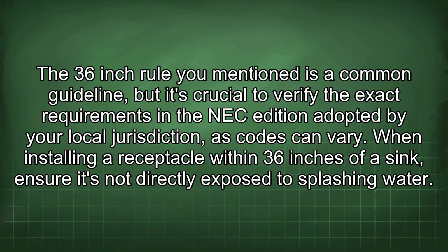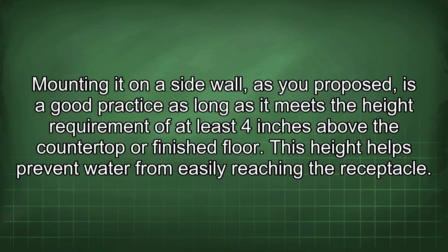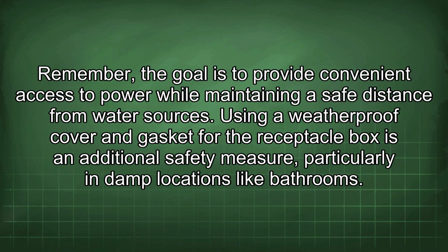When installing a receptacle within 36 inches of a sink, ensure it's not directly exposed to splashing water. Mounting it on a side wall, as you proposed, is a good practice as long as it meets the height requirement of at least 4 inches above the countertop or finished floor. This height helps prevent water from easily reaching the receptacle. Remember, the goal is to provide convenient access to power while maintaining a safe distance from water sources.